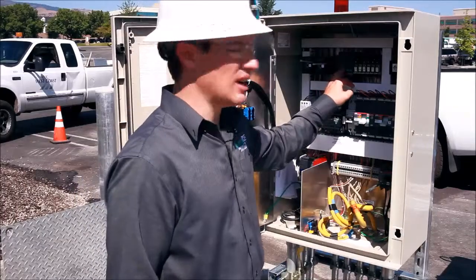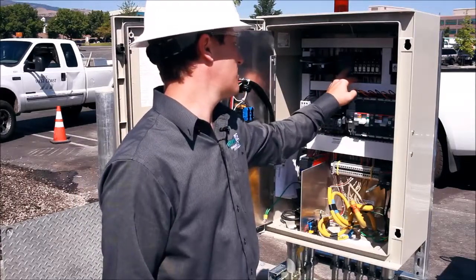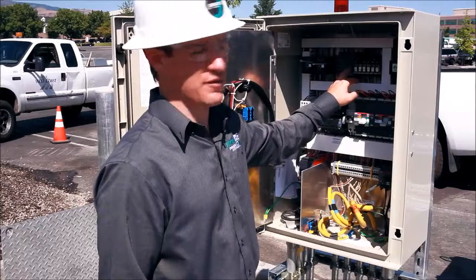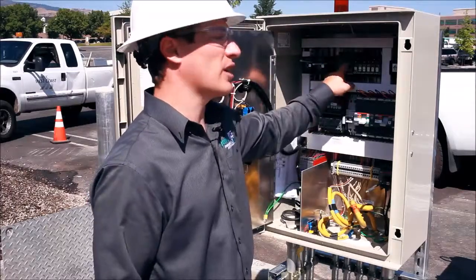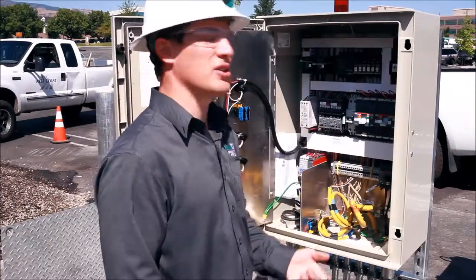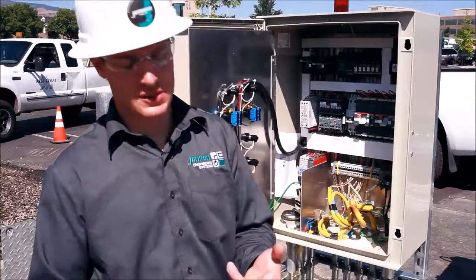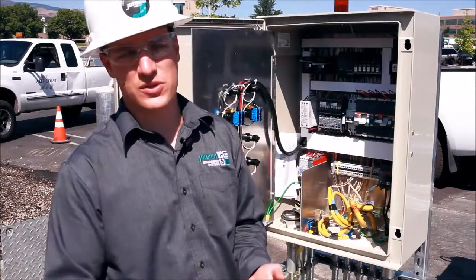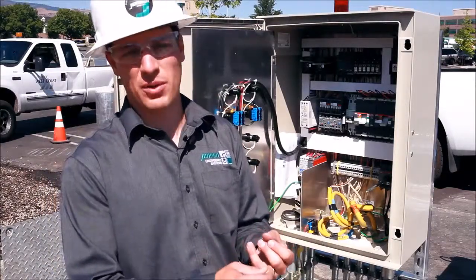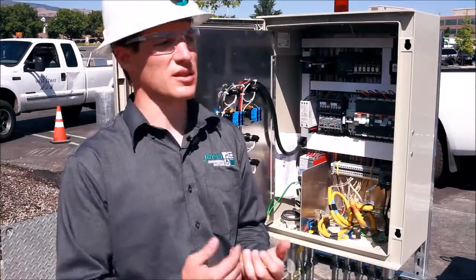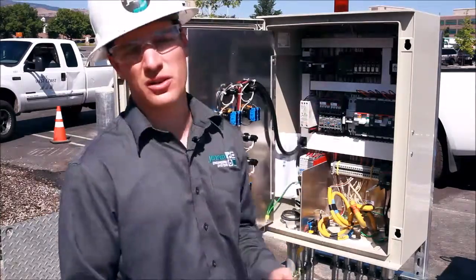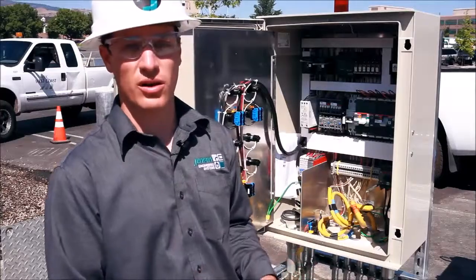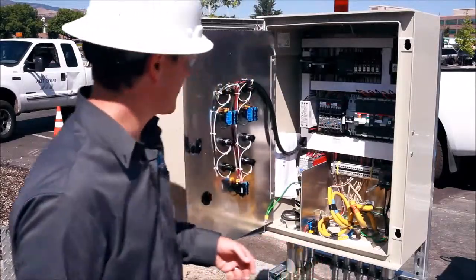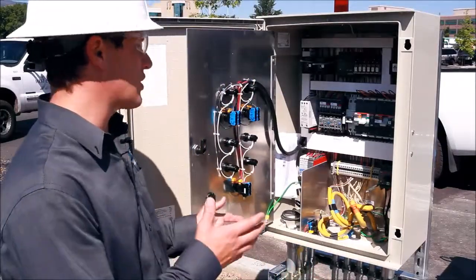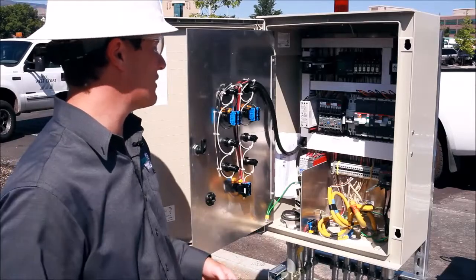So the PLC is a push button interface. You can move through the menus by moving up and down, left and right. In those menus, you'll see such things as run times, alarm counts, how many times the pumps have turned on, your inputs and your outputs, the date, the time, and then the very first screen will also tell you the actual level of the wet well as produced by the pressure transducer. So that's a good general overview of the components we have inside the control panel.